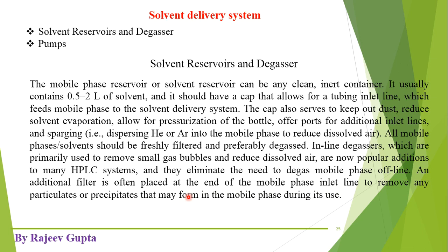If we see degassing, it could be done inline or offline. Offline degassing is generally used where a degasser is not already attached to the HPLC instrument. But if an inline degasser is attached, that degasser will remove any dissolved gases during the experiment. So this is the description of the solvent reservoirs and degassers of this HPLC instrument.